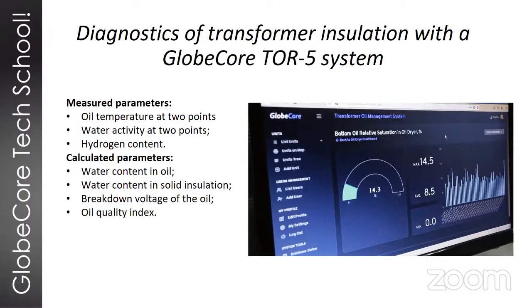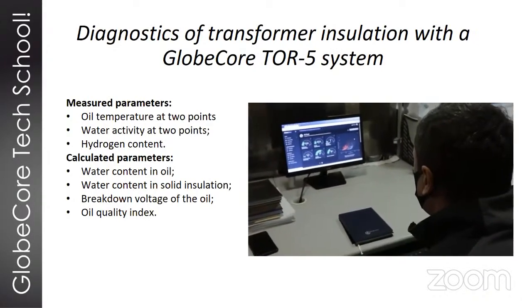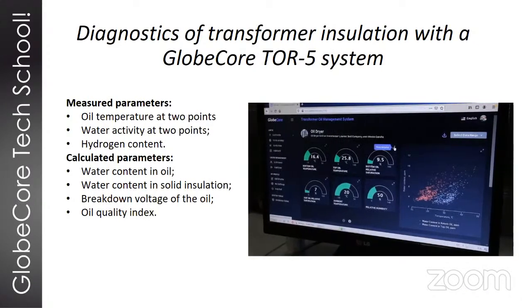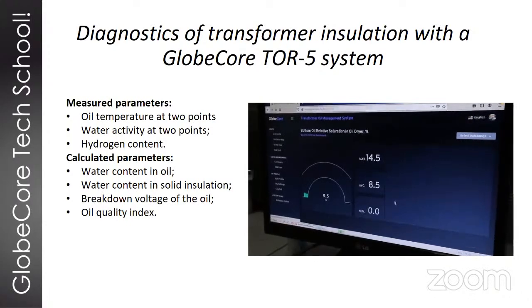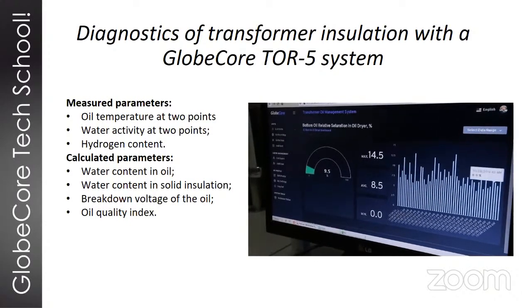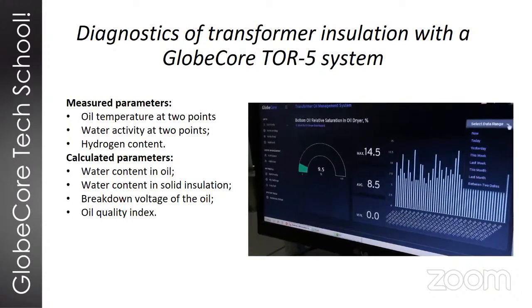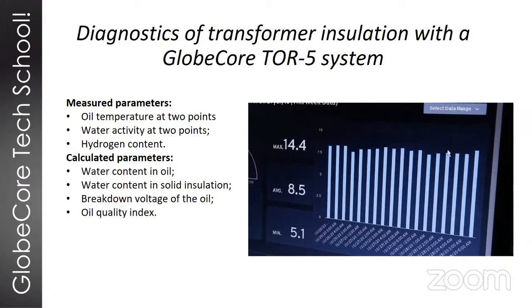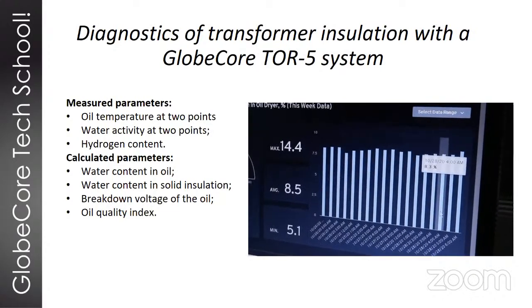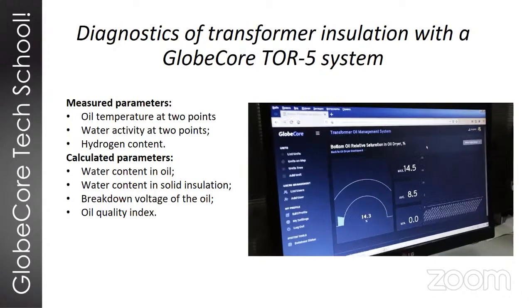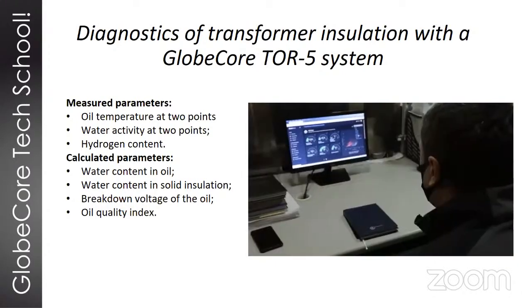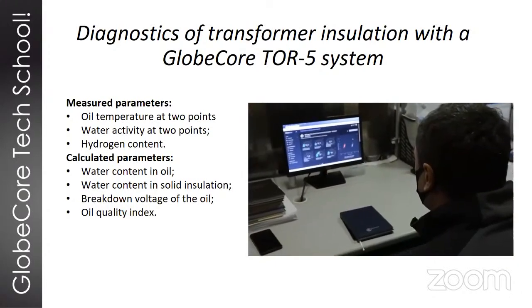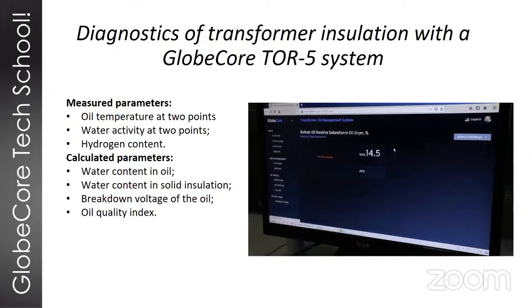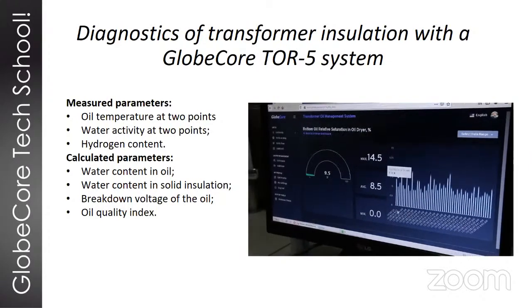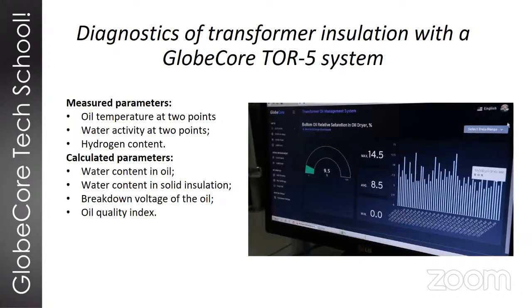The TOR5 sensors take readings once every minute, 24 hours, 7 days a week, and they take the following parameters. It takes the temperature of the oil at 2 temperature measurement points. It also takes water activity in oil from the transformer. This is recalculated into relative humidity. This is also done at 2 measurement points. And it also takes the amount of hydrogen in the oil.